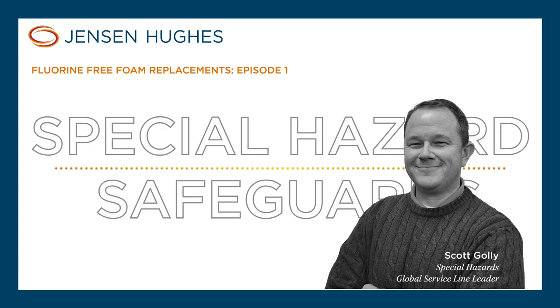AFFF was developed in the 1960s because of increasing hazards on shipboard applications in the Navy, and the Navy has led the way in its development. Initial military specifications were issued in 1969, and the first qualified products were delivered in the early 1970s. It's a synthetic foam made from chemical surfactants that produce a thin film — a low surface tension between the fuel source and the foam blanket. The PFAS component creates a nice film that acts as a polymeric membrane, producing a fuel vapor seal.